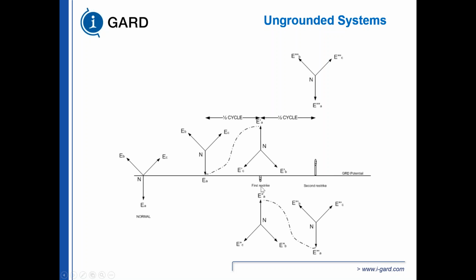Typically what's going to happen is the next restrike of the ground fault is going to be at the next peak sinusoidal part of the curve. So you're going to have a sparking arc when the sinusoid is at its maximum peak, and that's 1/2 cycle later. You could say this is the positive peak, this is the negative peak. So it's going to arc over, and you're going to shift that entire relationship down 2 per unit. 1/2 cycle later, you're up to 3 per unit. And the next positive restrike on the sinusoidal wave is going to shift this entire vector relationship up, and you can quickly get to 6 to 8 times the overvoltages with respect to ground.